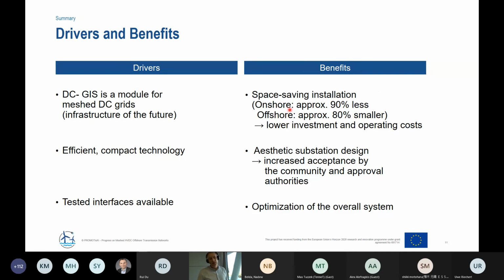And the benefits for us as user are space-saving installations. So maybe, as I already mentioned, the onshore is up to approximately 90% less and the offshore up to 80% less. So it means lower investment and lower operating costs. So maybe if the building is not so big, then also the operation costs are not so high. The next thing is aesthetic substation design. So maybe we have an increased acceptance by the community. Maybe as I explained, near to the beach, a building is accepted more than an AIS substation. It's a big part of discussion, and also the approval authorities maybe have an easier life with us if we have it in a building. And as I explained, we could also optimize the overall system. Maybe if we do not need such high lightning impulse voltage levels, or maybe we can also reduce everything. So the converter design could be a little bit smaller and so on.